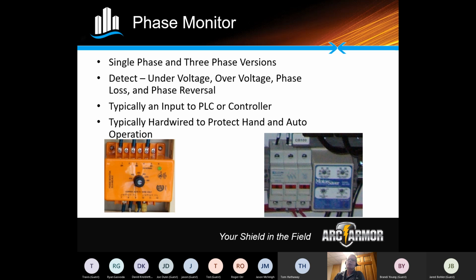Typically you're going to see a phase monitor installed where you're concerned about protecting motor equipment from running off balance, right? So if we lose a phase, or we're in an overvoltage or undervoltage situation, you want to protect that equipment. Primarily, you'll see a lot of these installed in panels that have full voltage non-reversing starters or across-the-line starters. Typically you would not necessarily need this in a panel if you're running drives. VFDs are inherently designed to protect themselves against these situations, but it's not uncommon to also see them in applications where drives are installed.